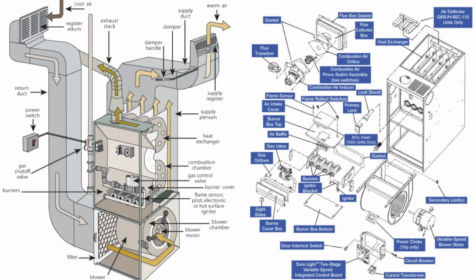I have two pictures of a couple of furnaces I want you to look at, but first we will go over this one. We're going to start on the left-hand side. This one actually feeds the return air from the side of it. It's not pulling it from the bottom as you would in a standard upflow in your home, where the return air vents are at the bottom of the base. This one would probably be more likely in a basement further up north where basements exist, and it will side feed. So let's start. You're going to have a return register where your cool air will be pulled into the return and then pulled down into the bottom part where the blower assembly is.